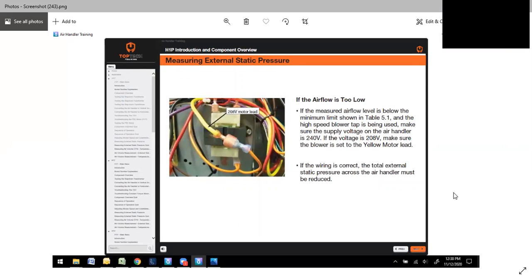If the airflow is too low, below 5.1, and the high-speed blower tap is being used, make sure the supply voltage on the air handler is 240. If the voltage is 208, make sure that the blower is set to the yellow motor lead. If the wiring is correct, the total external static pressure across the air handler must be reduced.